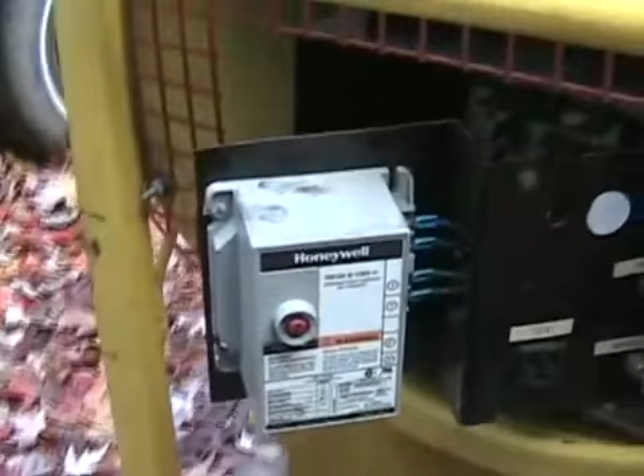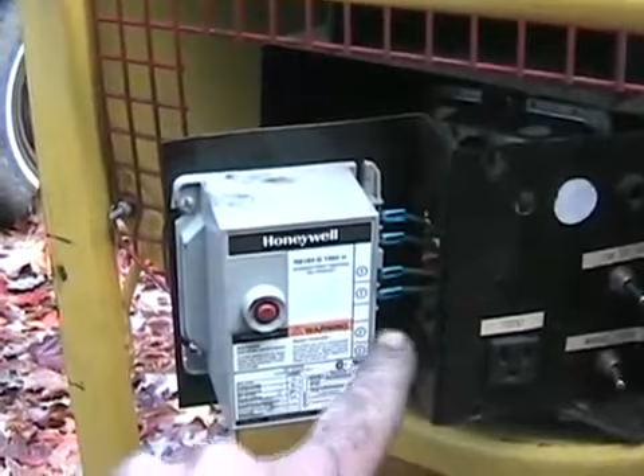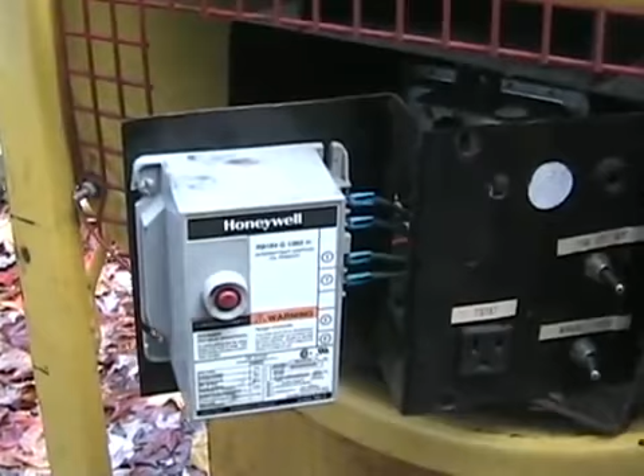On the business end of the unit, where all the power comes in, you've got your little brain box, and that's a reset button. The signal from your photovoltaic cell comes here, and the signal from that heat-sensitive switch comes here, the safety thermostat. So when you first turn this thing on to fire it up, obviously there's no light in the firebox, so that sensor senses darkness. So that little brain box has to first sense that it's dark in the combustion chamber, because of course that's what it is before you start it up. If it doesn't sense darkness first, then it knows the door is open and it's sensing light from outside, so it won't allow it to fire up, because you could get a blast of fire in your face and that would be, you know, not cool.